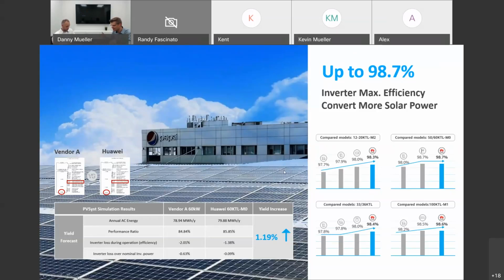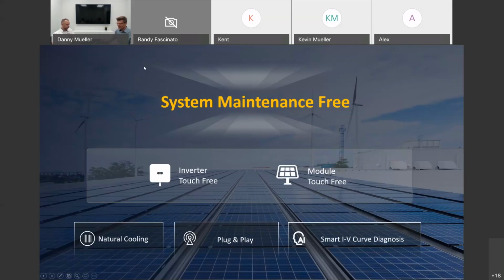And only as a secondary thought, you can look into what is my production gain based on the efficiency. And if you have a high efficiency inverter, let's say 98.0% CEC weighted efficiency versus the Huawei 45 KTL here, which is CEC weighted at 98.5, the delta is only very minimal, but you still get it. So it's still an advantage for you, but it's not the main focus point of inverter concepts today, and that applies pretty much to any inverter on the market from any manufacturer.